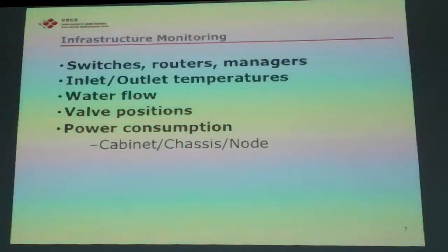Valve positions. Typically, these cabinets have a gate valve on them that will adjust automatically to control the flow of water based on demand of the cooling. What's the position? If you're running 100% open and your outlet temperature is continuing to rise, there's a problem.